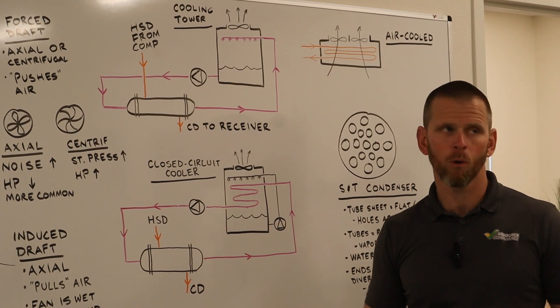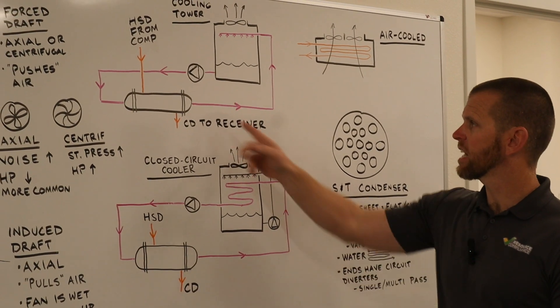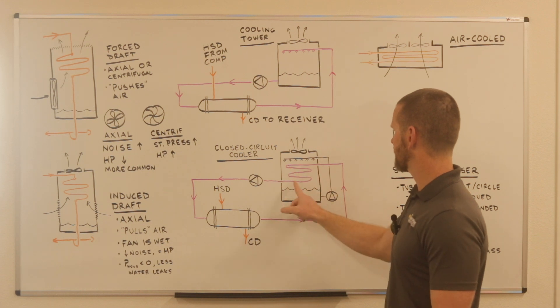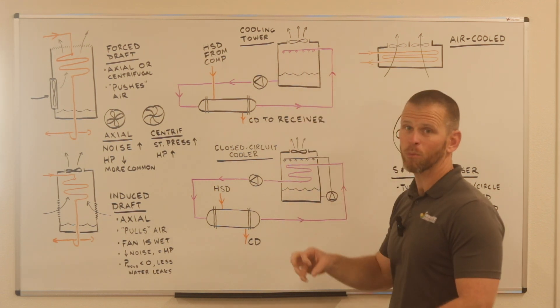But now we don't have two water loops anymore. We only have a single water loop. That's the major difference. So instead of the water being cycled through like it is in the closed-circuit cooler, instead it's just going to top and being sprayed over.